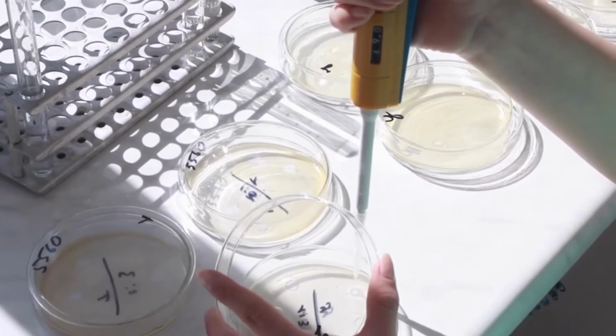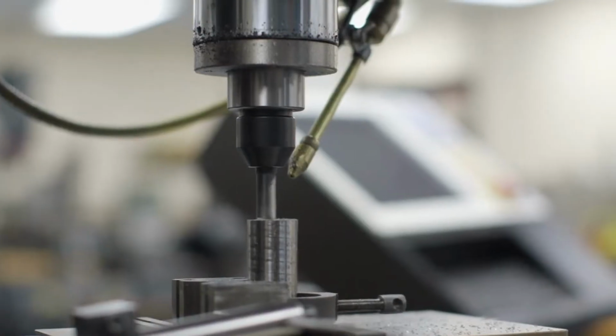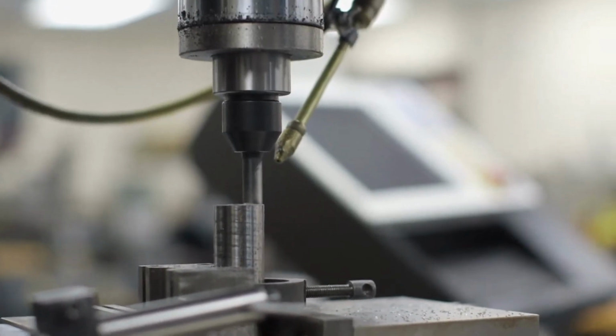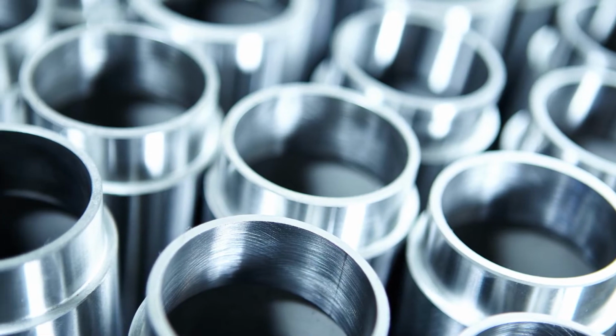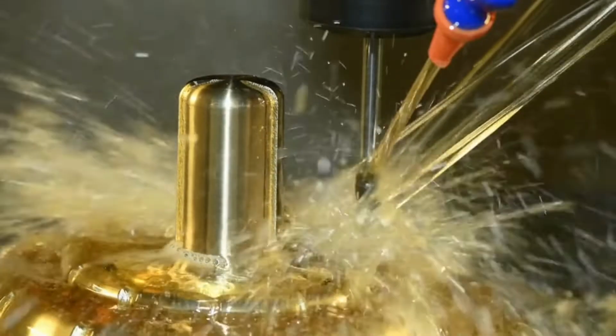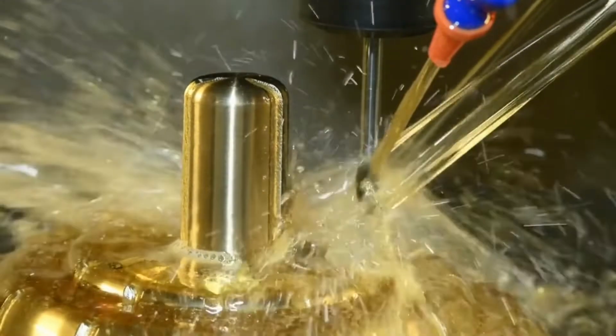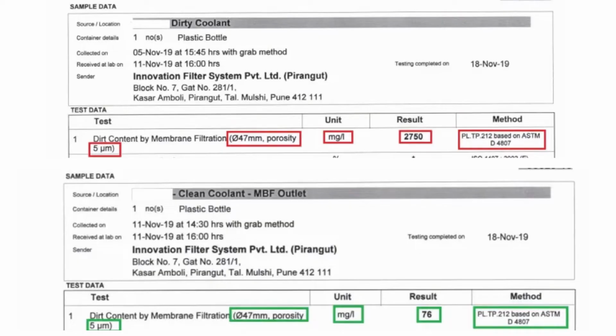First and foremost, let's try to understand what exactly is Millipore. Millipore is a test which is used in the industry, mainly in the manufacturing industry, to understand how clean your component is or how clean your process fluid is.